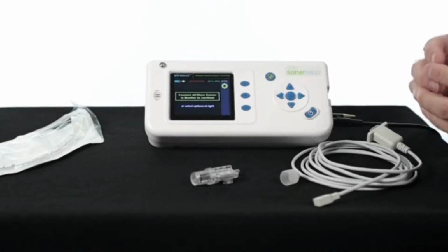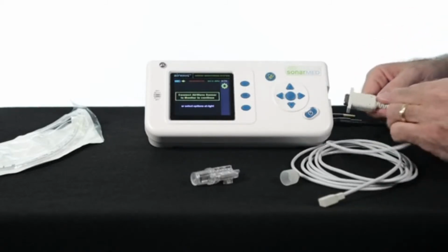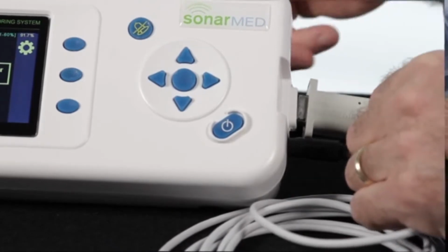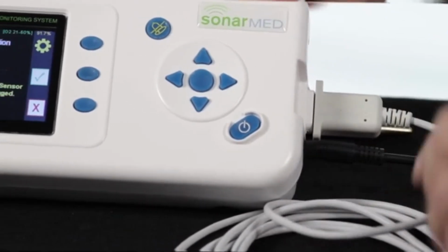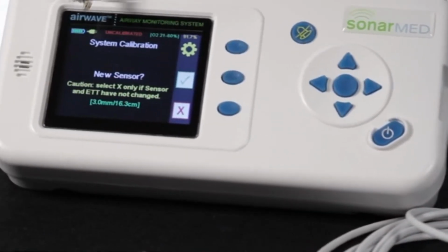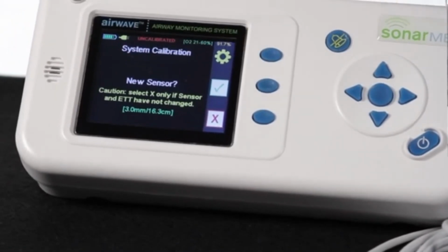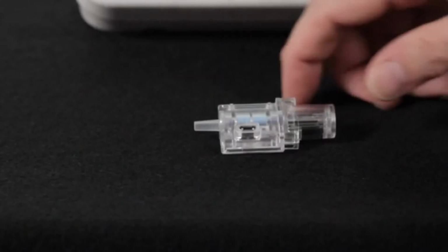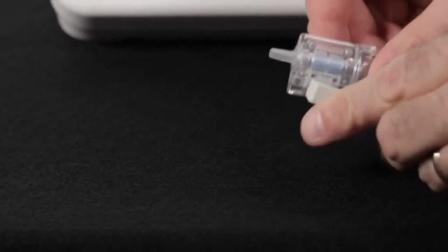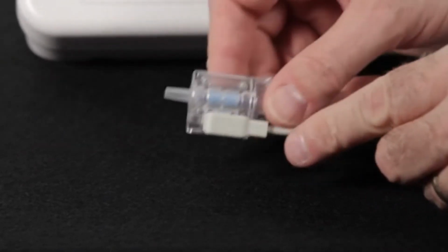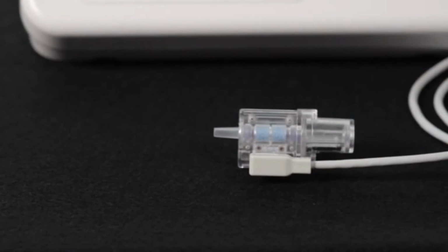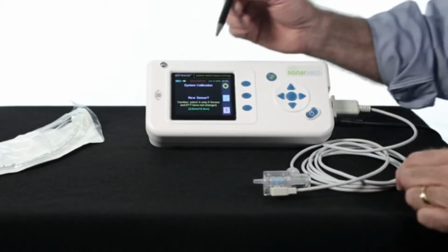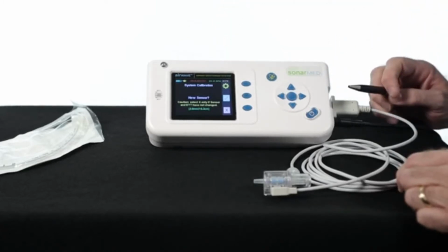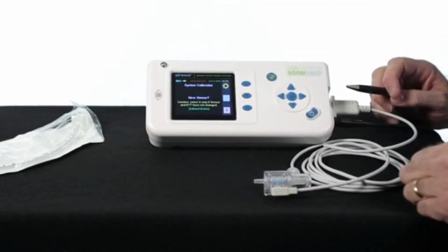So now we're going to set up the device to be used on a neonatal patient. The first thing we'll do is connect the cable, the sensor cable, to the monitor itself. And you can see when we do that, the screen pops up asking us if we're using a new sensor. We then will snap the cable into place on the neonatal sensor so that there's a connection between the sensor and the monitor. When you look at the monitor, you'll see first that the screen's changed to indicate that there's a new sensor once we plug the cable in.